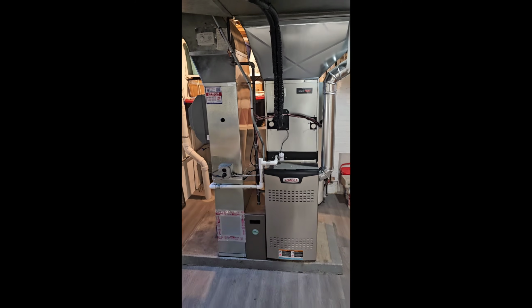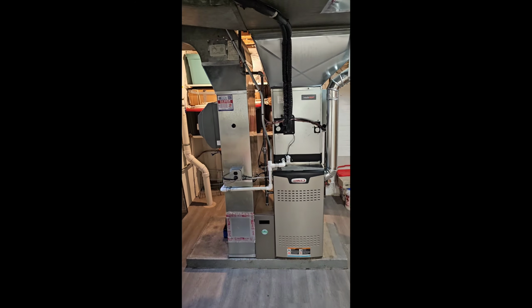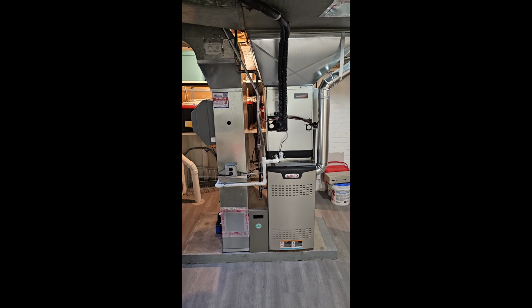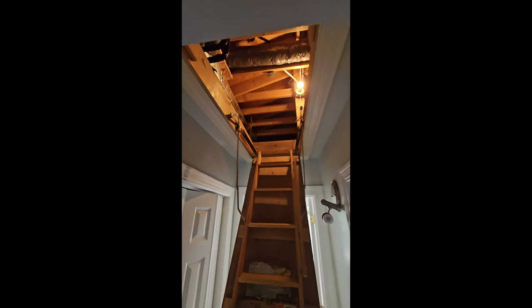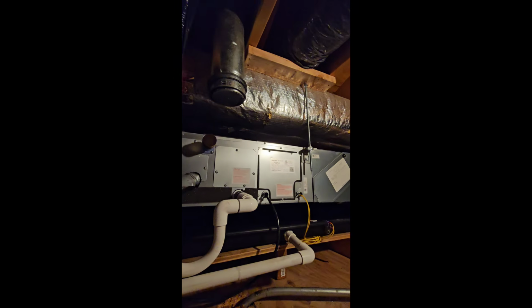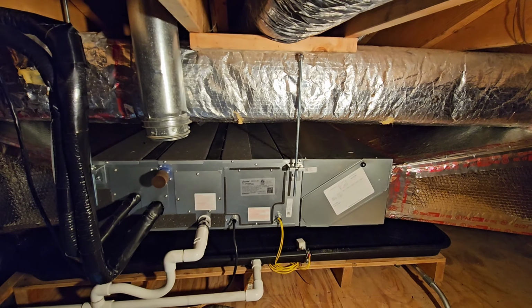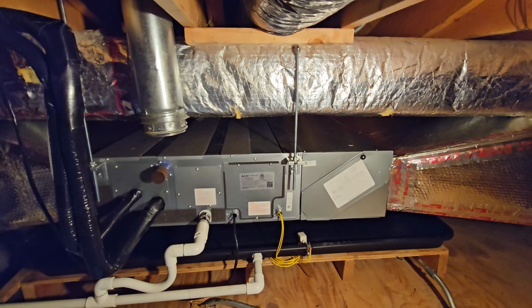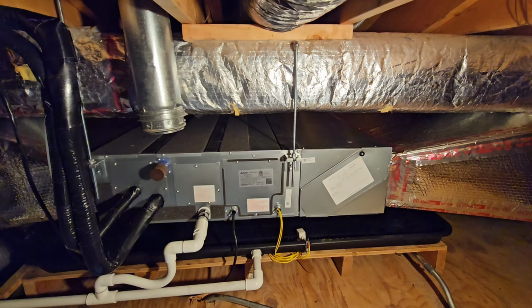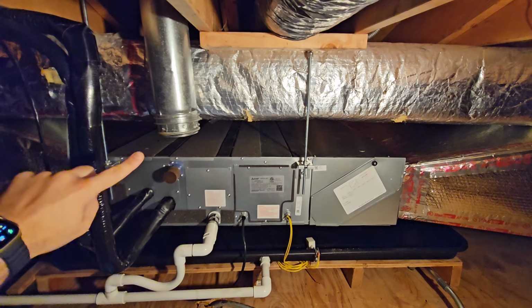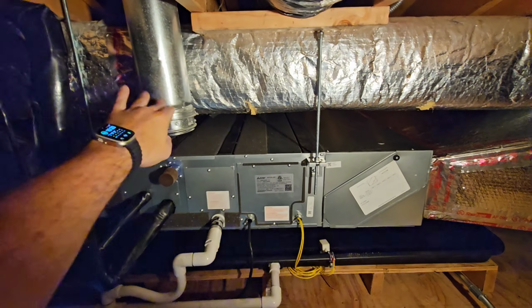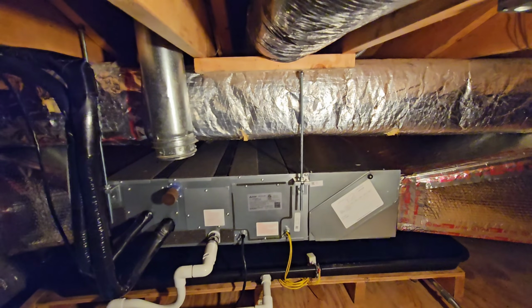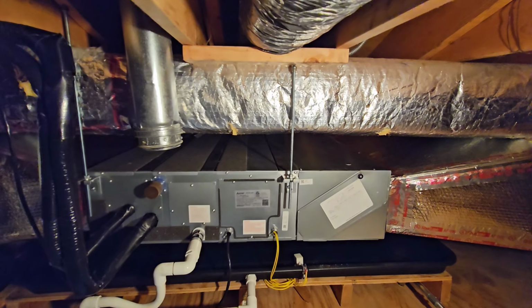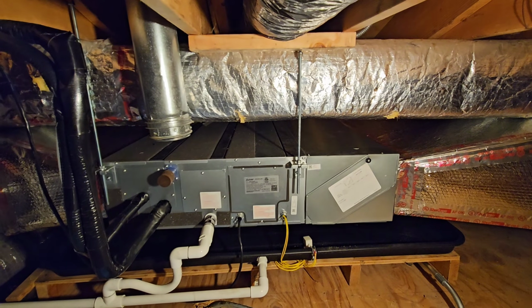And now we're going to take a look at our second indoor unit, which is the one for the second floor, which is an air handler in the attic. We'll take a look at that right now. So we're in the attic now. We're taking a look at the second zone of this multi-zone high-performance heat pump system. There used to be a gas furnace in here. Here's the chimney that we capped off. So one of the biggest issues in this setup is the space was way too small to have a gas furnace in here. It was crammed in there, no clearance for servicing it.